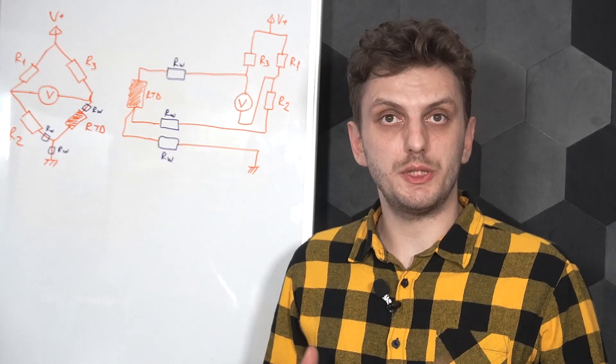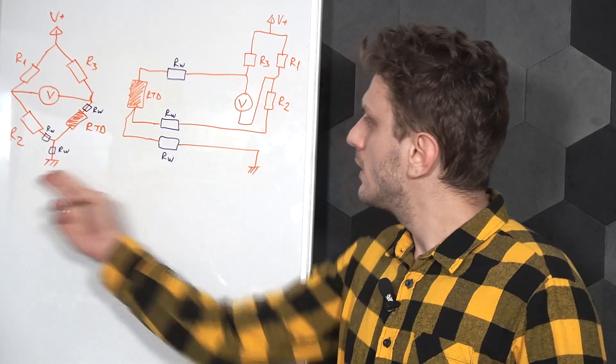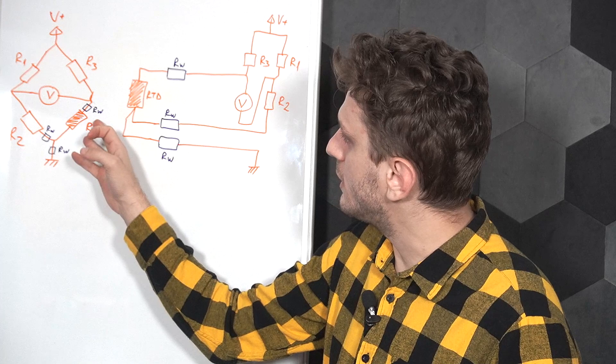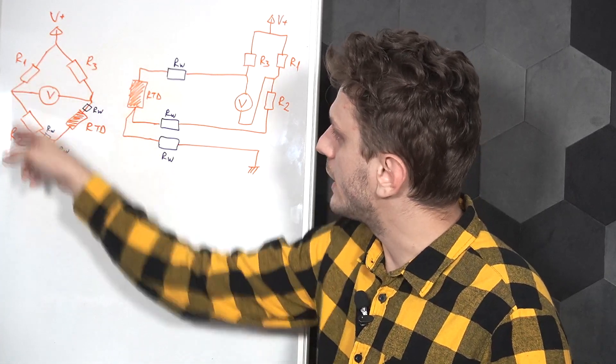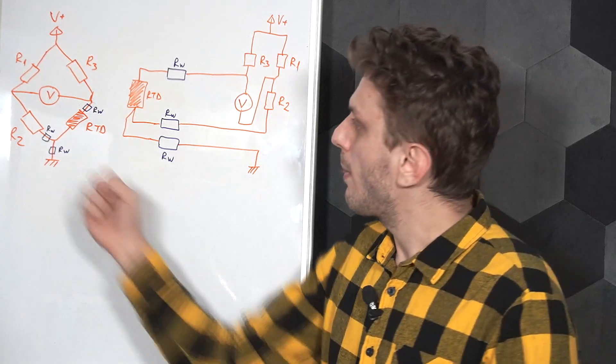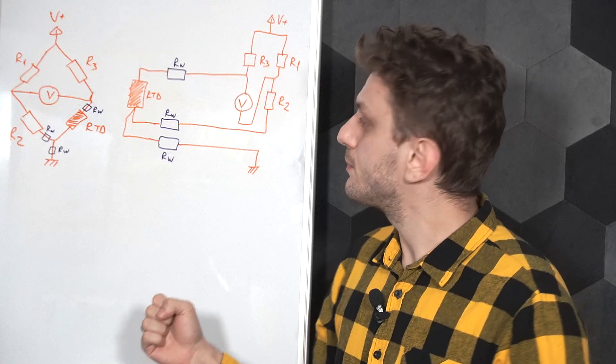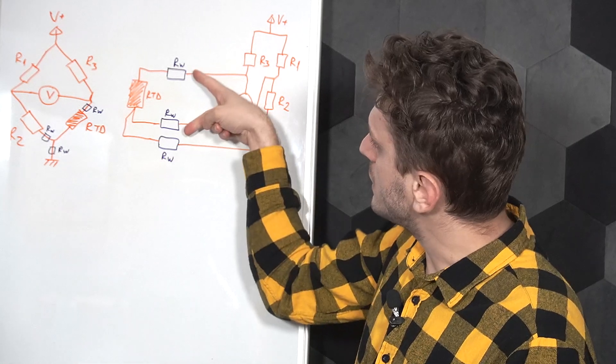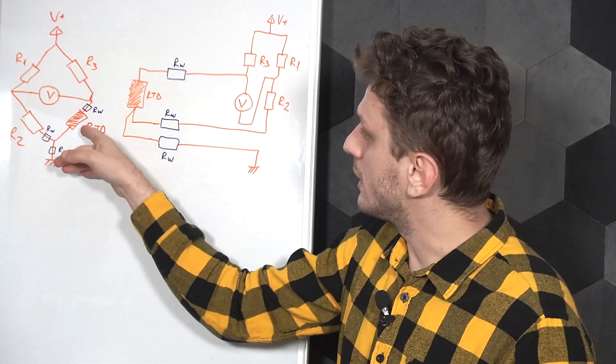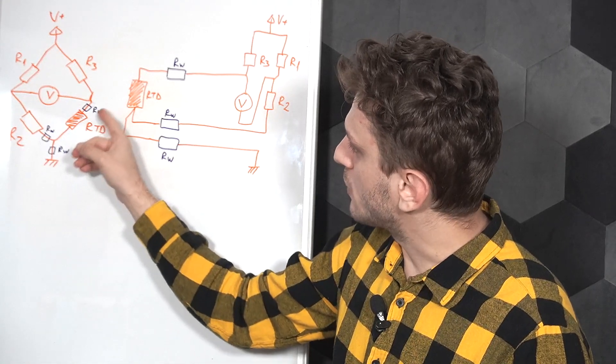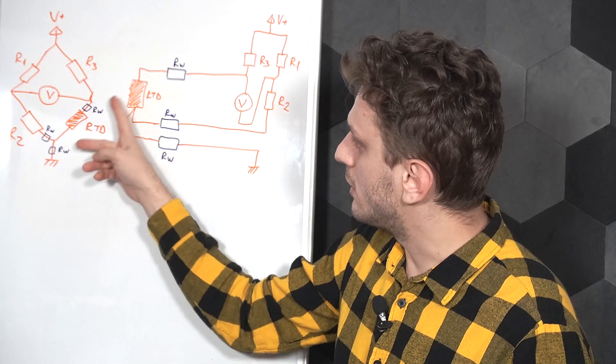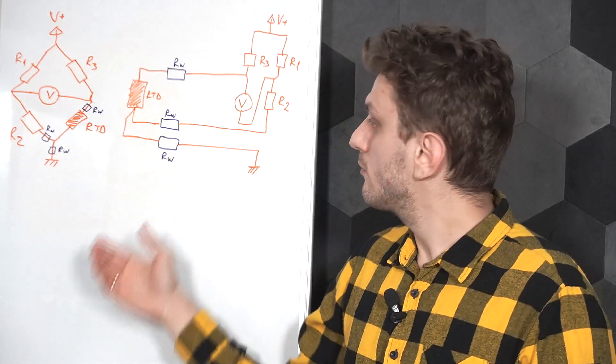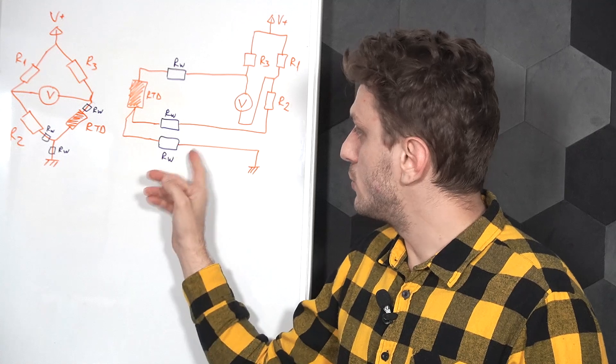The second method involves using a bridge measurement, but using only three wires. So these two circuits are equivalent. On one side we can clearly see the bridge measurement, so we have the RTD on one branch of the bridge, and then we have these other three fixed value resistors, and we're performing the measurement in between the two branches of the bridge. In the second drawing, we can see how the RTD is connected to the actual circuit. We're using two of these wires to connect the RTD to the bridge, and we can clearly see that one wire is in series with the RTD on one bridge, whereas the other wire is in series with R2 on another branch of the bridge, and then the bridge itself is connected to ground through the third wire.